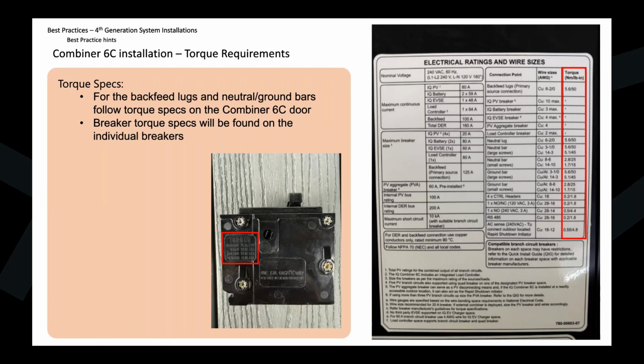Within the combiner, highlighted in red here on the right, we have torque specs for the neutral bar, the ground bar, and the back feed lugs. It specifically shows what wire size you're using, and those torque values might change slightly because of the different wire sizing. So we want to make sure everyone is properly torquing these correctly.